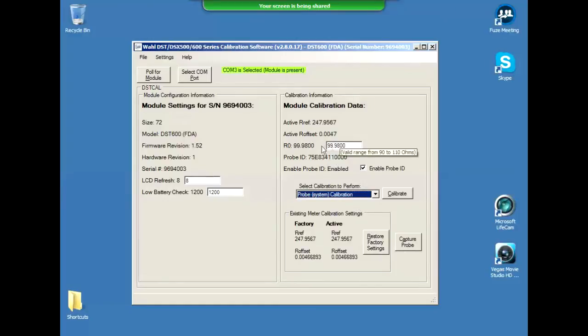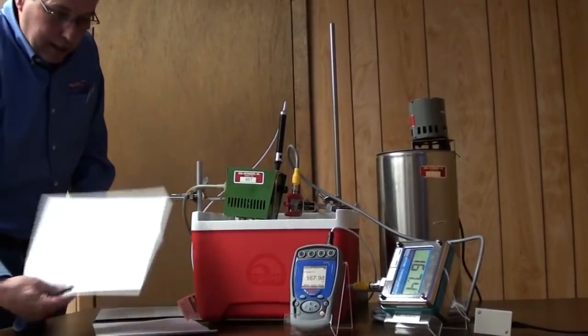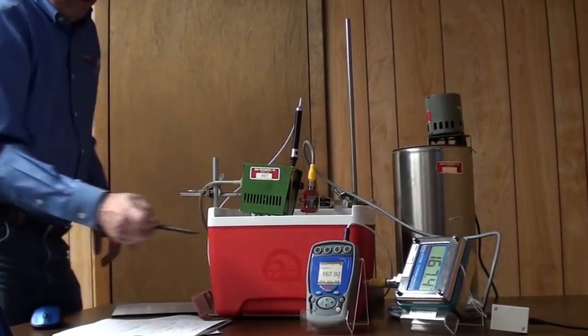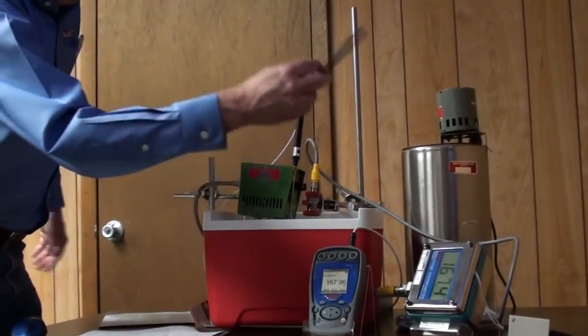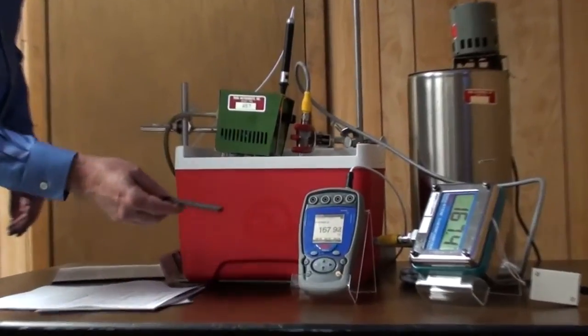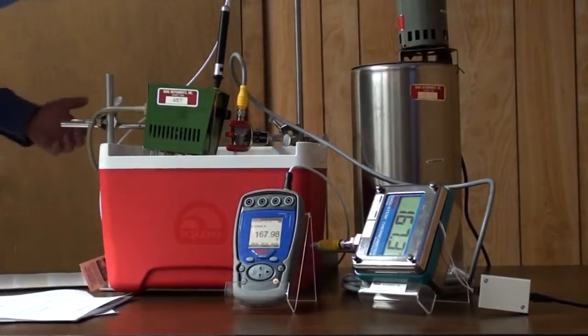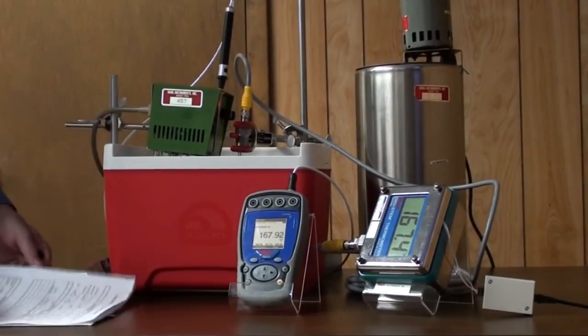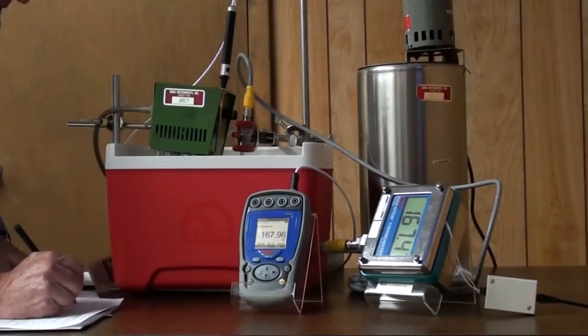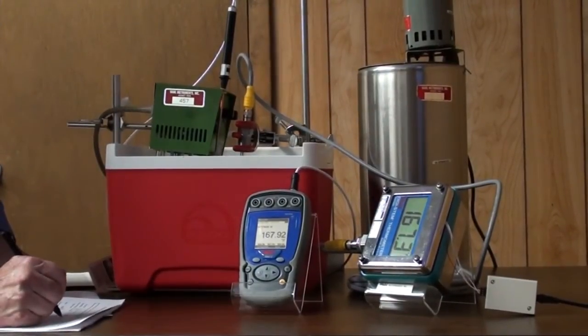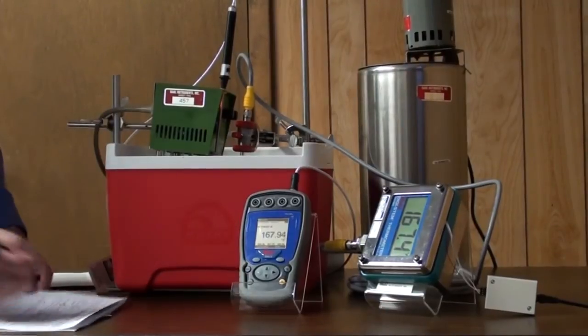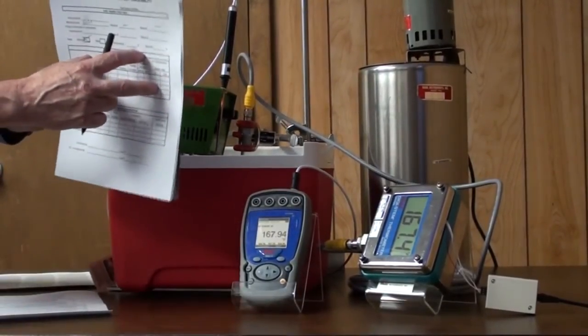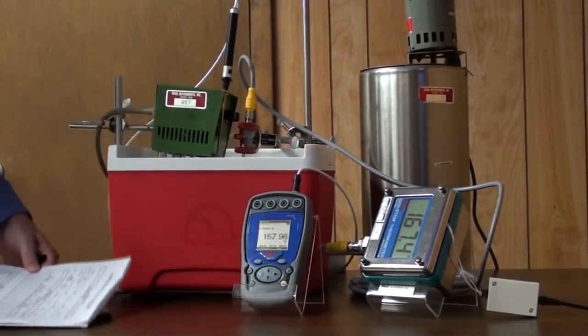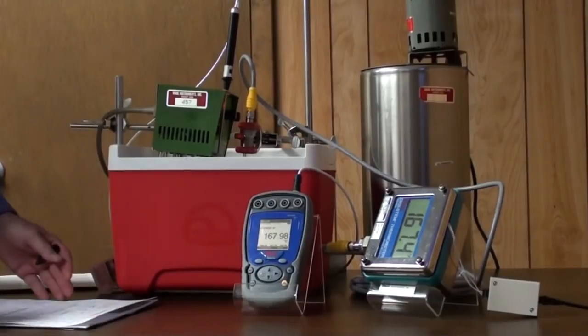Okay, so now we're going to go through this, and we're going to do before calibration, and I may be in and out of the picture here, I'm not sure. But I have my form here, I've got my procedure. We've basically got our bath and it's stabilized. Our meter is installed in the bath, and our standard instruments are in the bath, or our meter's probe is, okay? And I would fill out all my paperwork on here so that I write manufacturer, Wahl, and I'm not going to go through this, model number, serial number, and I'm taking before data. Some forms it's possible to put before data here and after data here and do it all on one form, and that's really how most of ours are. It's just this sample wasn't.